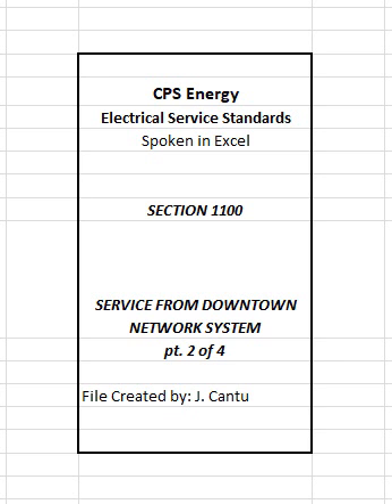I. Lighting. Transformer vaults or rooms shall be electrically lighted. CPS Energy will install lighting and associated circuitry. Customer circuitry shall not be used. J. Inspection. A series of critical inspections will occur during construction of the customer-built transformer vault or room to verify that it is constructed in accordance with CPS Energy specifications.